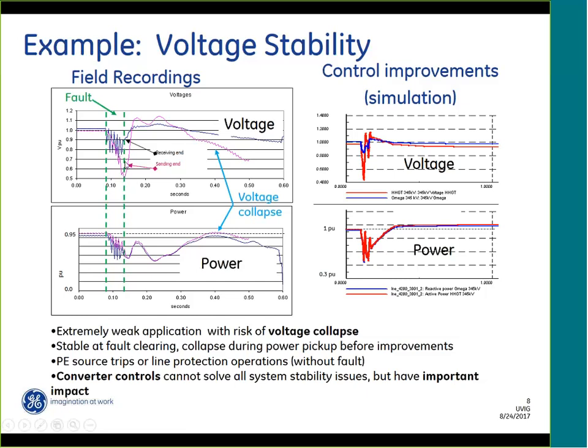At the time the fault is cleared, the system recovers well. The voltage comes back to nominal and a bit higher because the active power is relatively low. After a transient of around 250 milliseconds in this time scale, we see that the power starts recovering. That is, the wind turbines start ramping up the active power to go back to where they were initially. And you can see how the active power goes back to the initial value. Now, in that exercise of increasing the power, we see that the voltage is coming down. And in fact, it ends up collapsing. So the increase in active power results in a decrease in voltage that ends up collapsing the system. This is voltage stability in this environment with renewables.